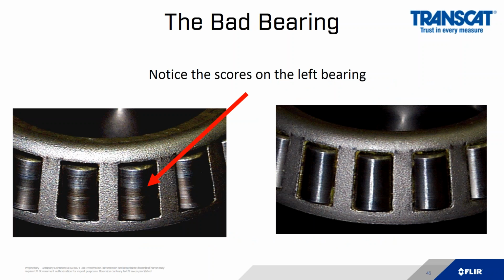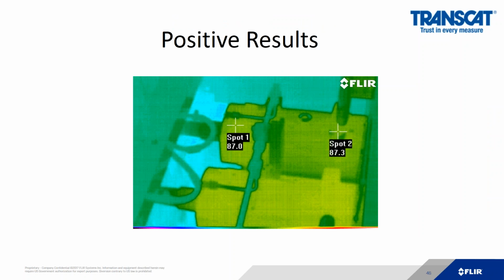When we opened it up, we could see the scoring and the brinelling on the bearings on the left-hand side of this picture. If you look at the left-hand side compared to the right-hand side, you can see the much smoother thrust bearing. Once we installed the thrust bearing, the motors returned back to the same temperature, thereby avoiding a catastrophic failure. That is simple return on investment 101.